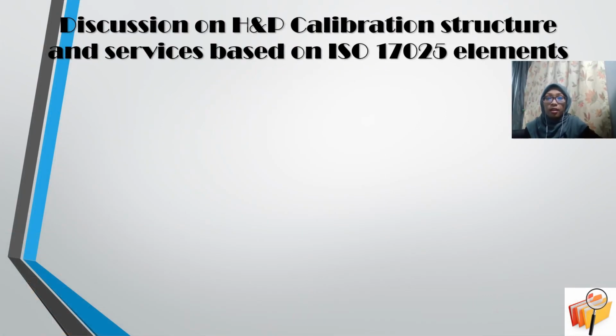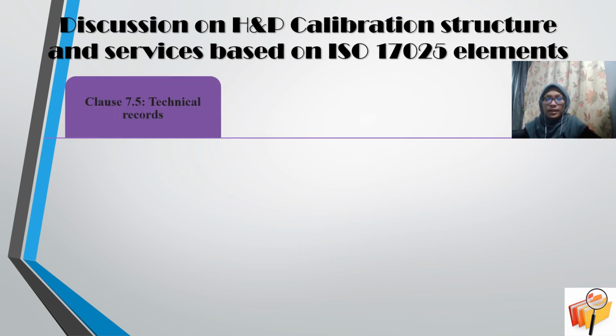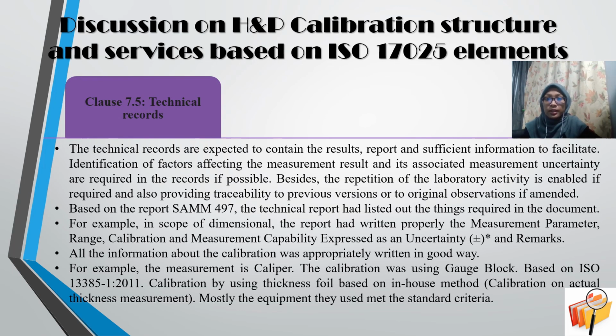H&P calibration has clause 7.5, which is technical record. The technical records are expected to contain the result report and sufficient information to facilitate identification of factors affecting the measurement result, and associated measurement uncertainty is required in the records, if possible. Besides, the repetition of the laboratory activity is enabled if required, and it also provides traceability to the previous version or to the original observation if amended. Based on the report as SAMM 497, the technical report has listed out the things required in the document.